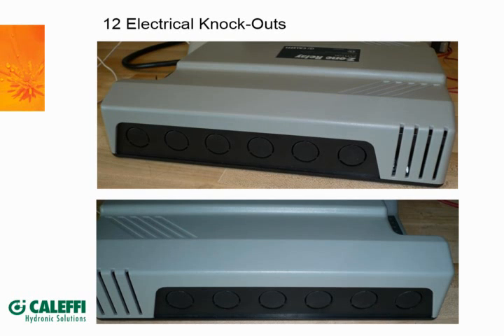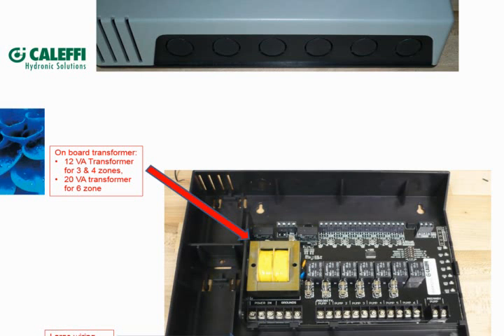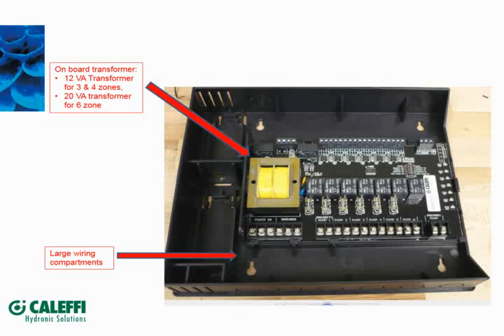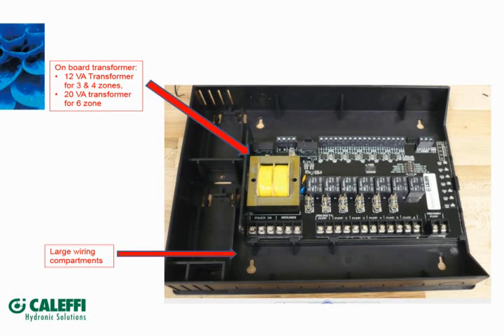And once you open it up, you're going to see we got a lot of room. We got a large wiring compartment in here to make it easy to get those wires in. So if you got big fingers, trying to get in there, it will give you a lot of room. The 3 and the 4 zones come with a 12 VA transformer. This transformer is really only powering the thermostats and a little bit on the control board. The 6 zone comes with a 20 VA onboard transformer. And that's mainly for power stealing thermostats or something like that, so there's enough available current. Yeah, either power stealing or a 3-wire.